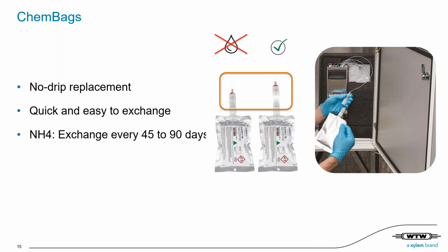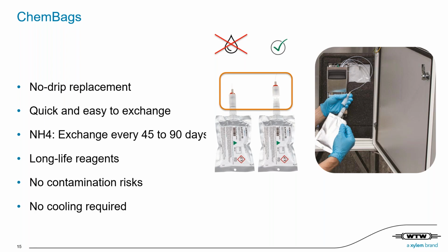Thanks to the low reagent consumption realized by the new MultiPort valve technology, the exchange is only needed once every 90 days for measurement range 1 and every 45 days for measurement range 2 at a 10 minutes interval. With longer intervals, the lifetime is even longer. Another benefit is the long shelf life of the reagents. Thanks to the ChemBags, the risk of contamination and fouling of the reagents is eliminated, as the reagents don't get contact to the air, for example. So in addition, the reagents don't need to be cooled, but can be stored at room temperature between 18 and 28 degrees over 1 year.